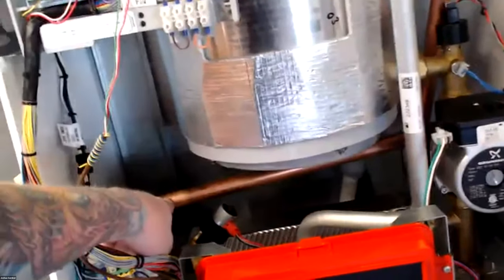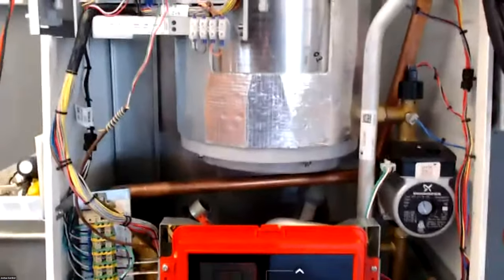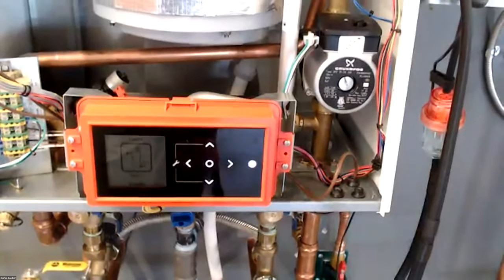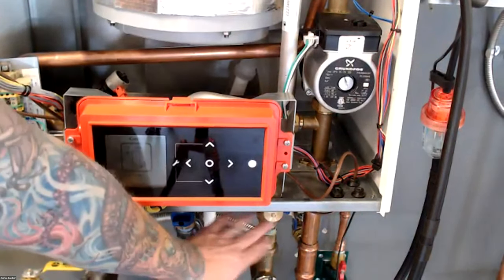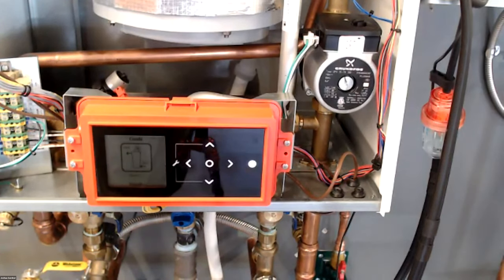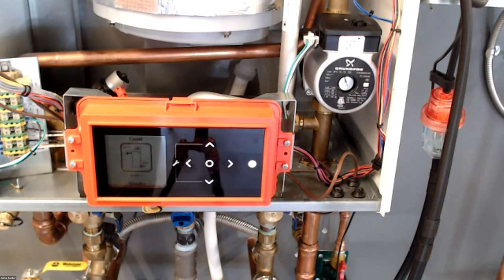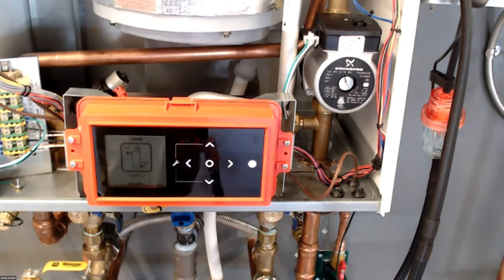Oh, okay. So that three-way valve too. One thing to note with the troubleshooting and setup is your three-way valve diverts your supply water to the system or to the heat exchanger. And when it does that, it cuts the system off thermally to your thermal expansion. So it is important, if you are doing a combi, to make sure you don't have a check valve on the return boiler piping. If you have a check valve going towards the boiler on the return piping, and you go into domestic, your boiler is then completely cut off from any thermal expansion. So there's no need for it, and there's no reason to put a check valve on the boiler return line going into it.